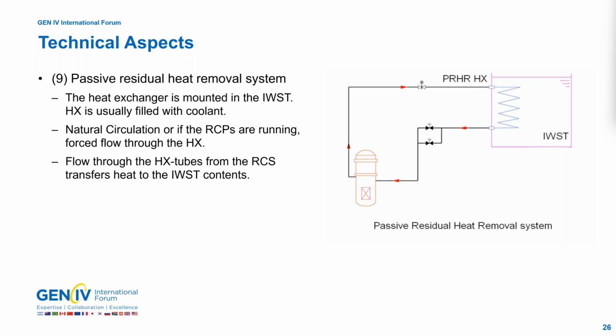The passive residual heat removal system: we know the heat exchanger is mounted in the inner water storage tank. Heat exchanger is usually filled with the coolant. Natural circulation from the reactor core to the inner water storage tank, and transfer the heat from the core to the inner water storage tank. Next, please.